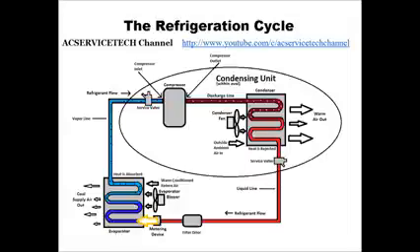The refrigerant is actually absorbing heat once it enters the evaporator coil. As it absorbs enough heat, it turns into that saturated state in the middle of the evaporator coil, where most of the energy absorption is taking place. Right after the saturated state, it turns into a low pressure, low temperature vapor.